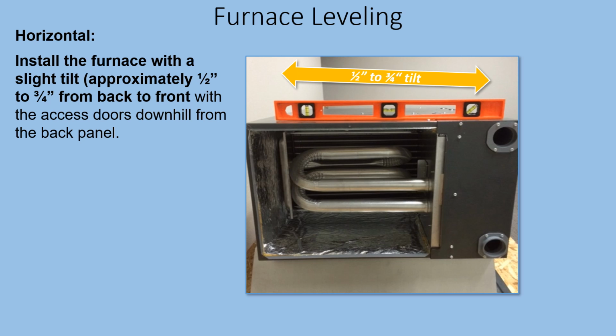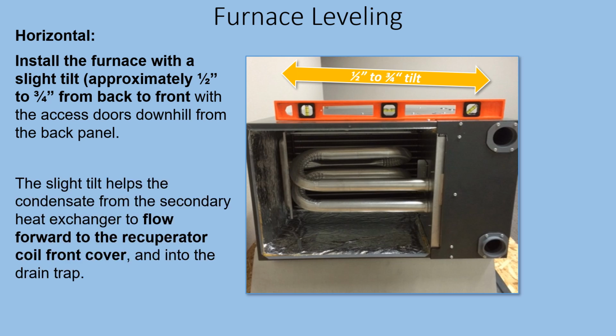Horizontally, install the furnace with a slight tilt, approximately 1/2 to 3/4 inch from back to front, with the access doors downhill from the back panel. Because obviously we want that pitch going from the back to the front, to force the water to roll down to the drain and flow to the recoup cover, front cover, coil, whatever you want to call it, into the trap.